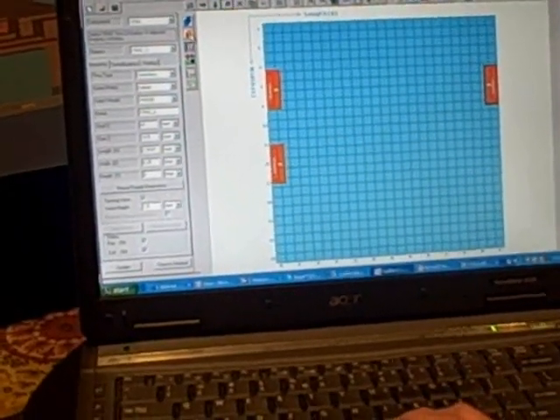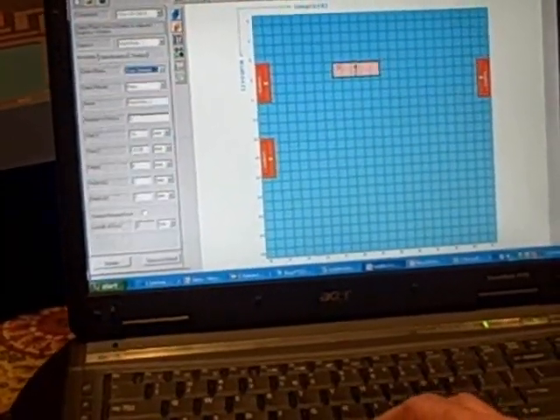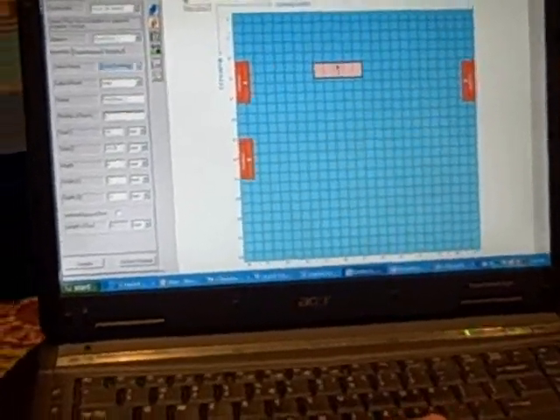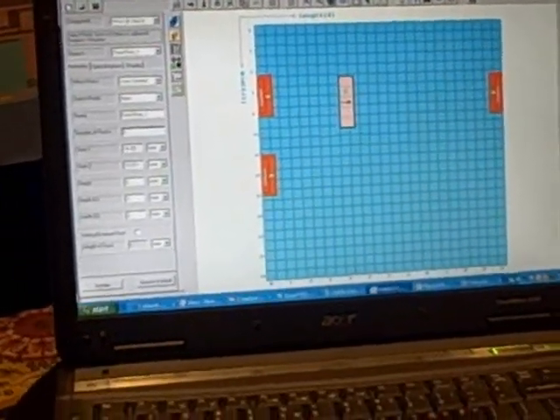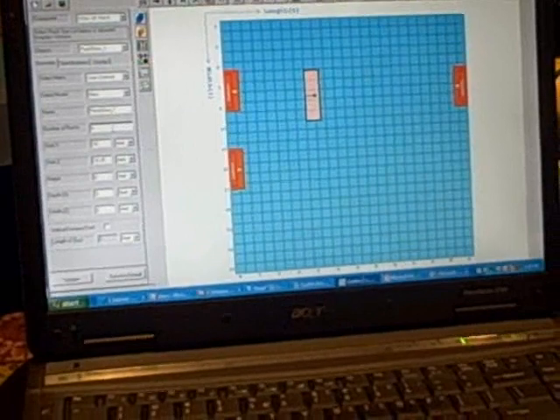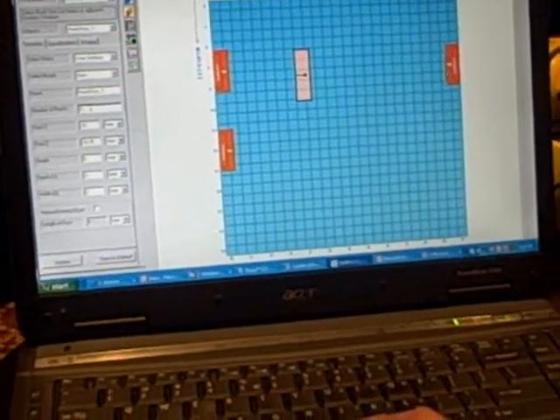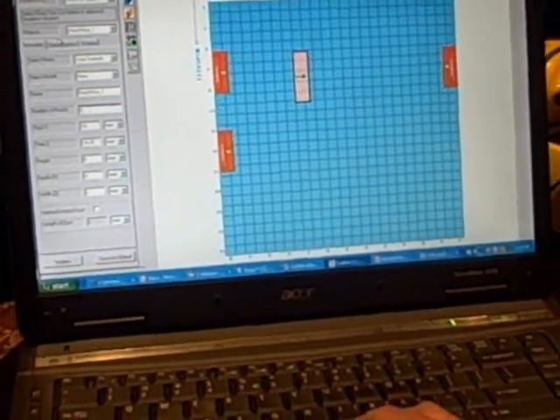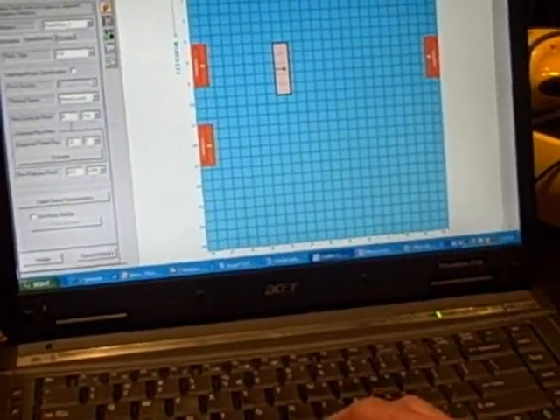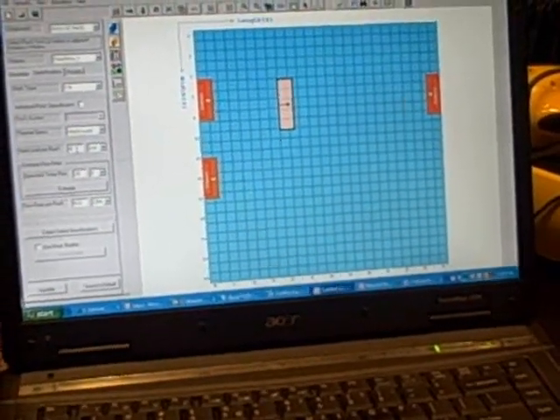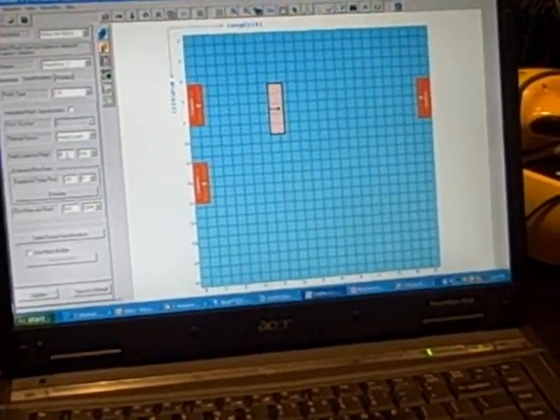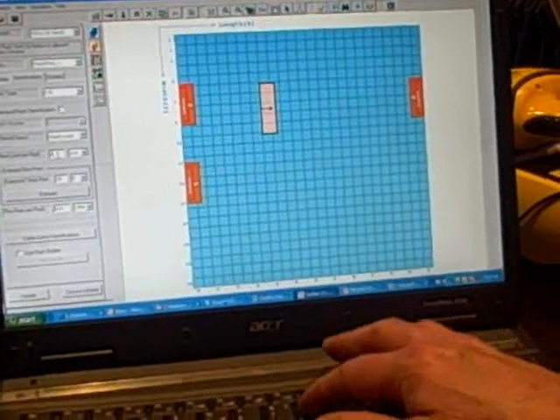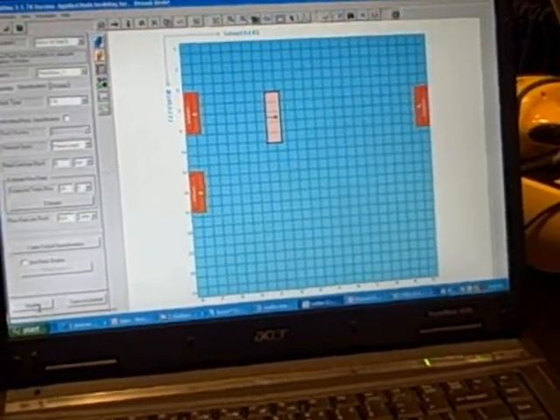To model racks we simply take the rack tool and drop it in, orient the rack in the correct direction. There's our first rack. This is a rack row of five racks. And the way we model them is to model them as an average heat load per rack. It defaults to four kilowatts. We can change it to be whatever we want. That is one method for modeling it.